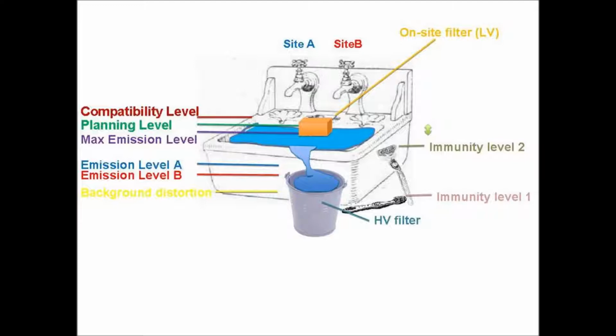So in this case, we've got a little hole there where the water can flow over if it gets too high. The planning level is basically where 61000-3-6 comes into play. Eirgrid uses that and allocates to the planning level with a margin maintained. And then the maximum emission level, that's really the last chance saloon. You don't want to go beyond that. You want to retain that margin at all times before you hit the planning level, because things start to get hairy at that point. So that's the three levels everybody talks about.